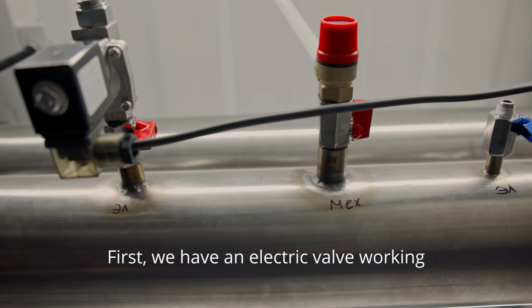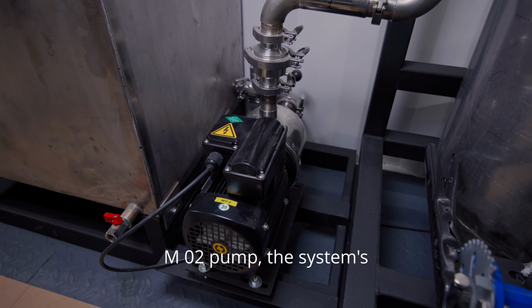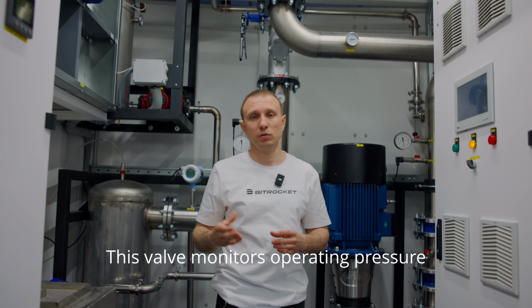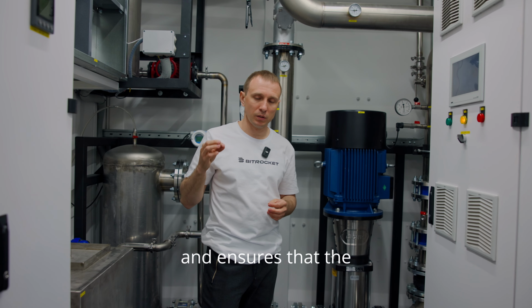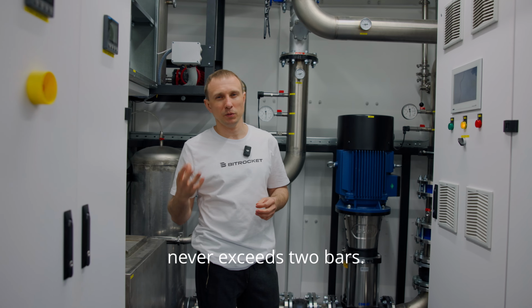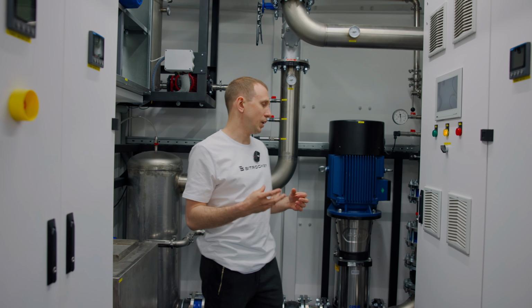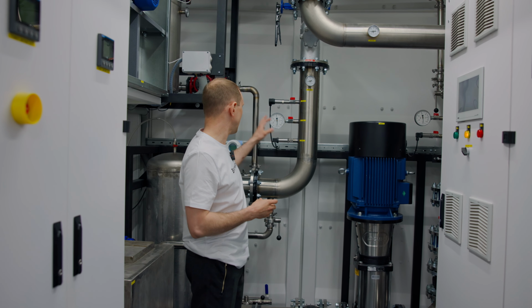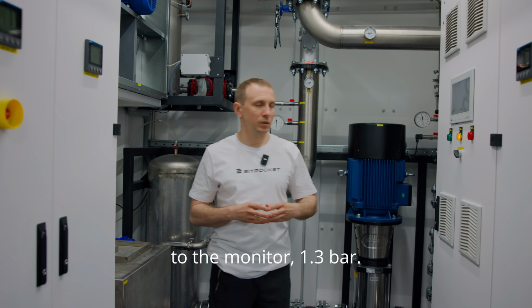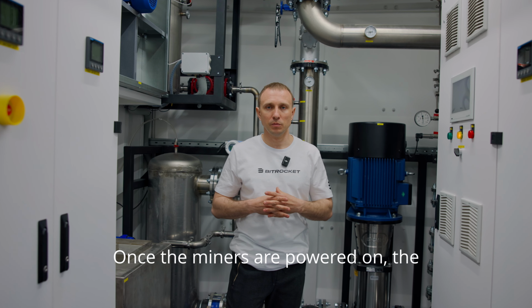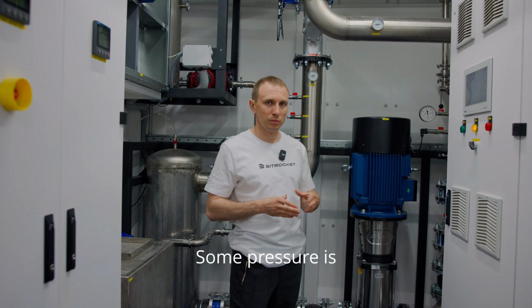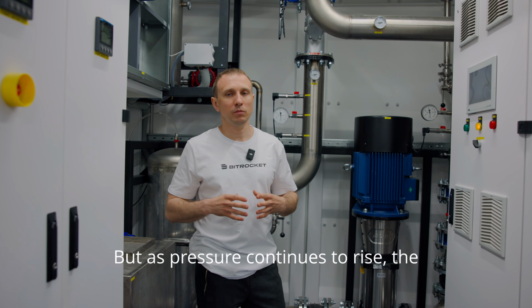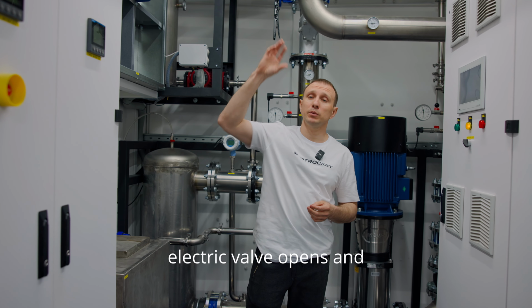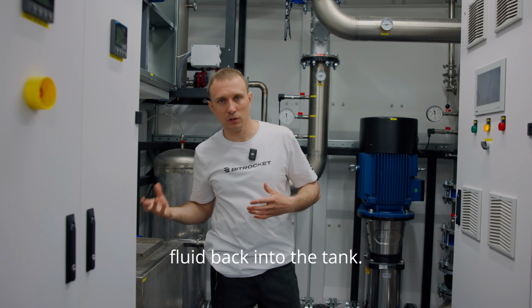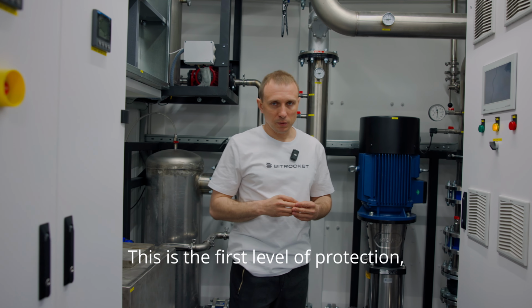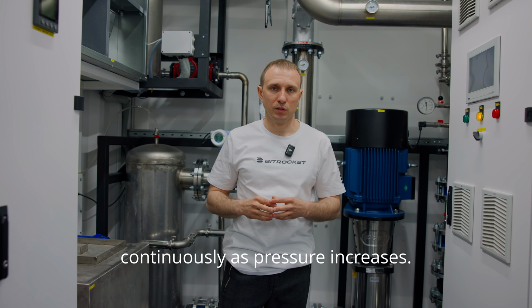First, we have an electric valve, working in conjunction with the MO2 pump, the system's top-up pump. This valve monitors operating pressure and ensures that the pressure on the discharge line to the miners never exceeds 2 bars. Here's how it works. When you start the system, pressure is at a certain level. In this case, according to the monitor, 1.3 bar. Once the miners are powered on, the system begins to expand. Some pressure is absorbed by the expansion tank, but as pressure continues to rise, the electric valve opens and redirects excess expanded fluid back into the tank. This is the first level of protection, and it operates continuously as pressure increases.